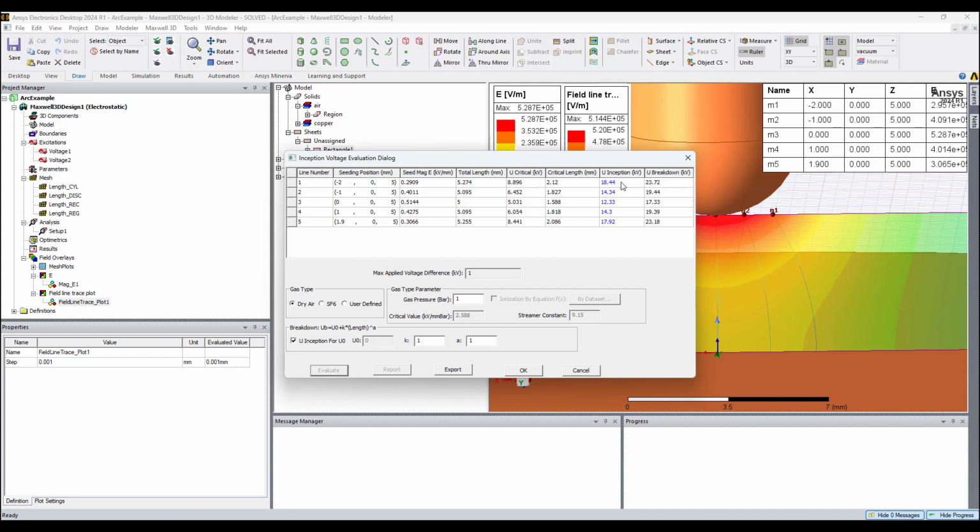If the inception voltage is reached, then the local polarization will take place, which basically redistributes charge in the dielectric, and this happens effectively when there are voids and defects in the material. So the more defects and voids in the material, the stronger will be the redistribution of charge in the dielectric. All right, and here we see the total length of the arc.